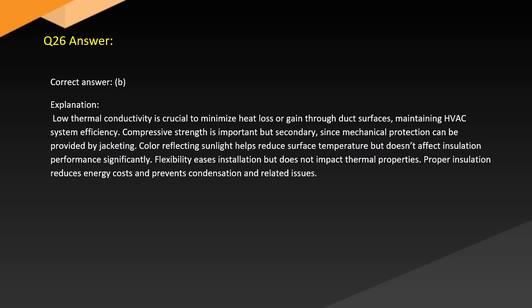Answer. Correct answer: B. Explanation. Low thermal conductivity is crucial to minimize heat loss or gain through duct surfaces, maintaining HVAC system efficiency. Compressive strength is important but secondary since mechanical protection can be provided by jacketing. Color reflecting sunlight helps reduce surface temperature but doesn't affect insulation performance significantly. Flexibility eases installation but does not impact thermal properties. Insulation reduces energy costs and prevents condensation and related issues.